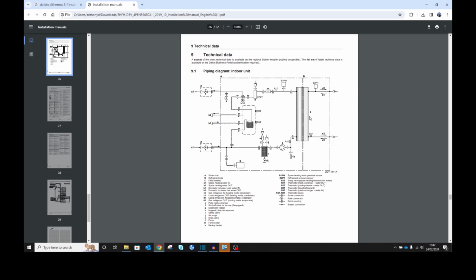So on the left side of the heat exchanger, we have got a backup heater here, and we also have a circulation pump here. We have got thermistors for your flow and thermistors for your return, and then another thermistor for the flow out of the backup heater, and then we've got a three-way valve. This valve will send heating medium out to the central heating circuit, your radiators, or it will send it into this heating coil for the built-in hot water cylinder.